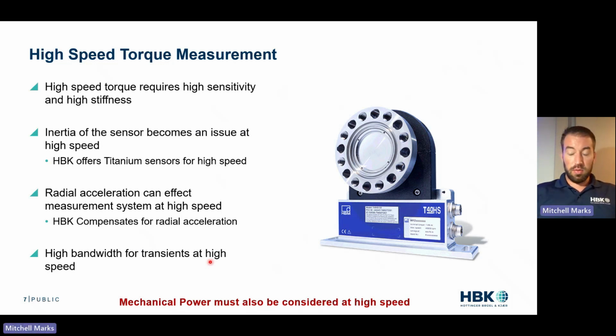If you're at high speed and you apply a transient, you might actually miss that if you have a really big filter on your sensor. You might miss it at low speed if you have a big filter on your sensor, but especially at high speed. So check the bandwidth. HBK offers 6 kilohertz of bandwidth. Again, we have some really nice webinars on measuring torque ripple and dynamic torque if you are interested. But mechanical power must also be considered at the high speed, especially under the transients. So you don't want to be damaging your sensor or getting an incorrect reading because the thing is pulling itself apart.